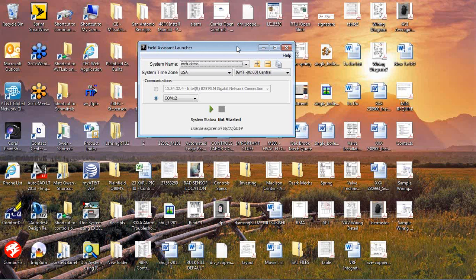Okay, so if I have 5 Carrier rooftop units wired together, if I plug this Field Assistant software into one of the controllers, I can actually see and configure all 5 rooftops from just one location. And to go one step further, if you provide a Carrier communicating sensor along with those rooftop controllers, you can actually plug in locally to that sensor. You do not have to plug in at the controller itself on the rooftop. So kind of a nice little deal there.